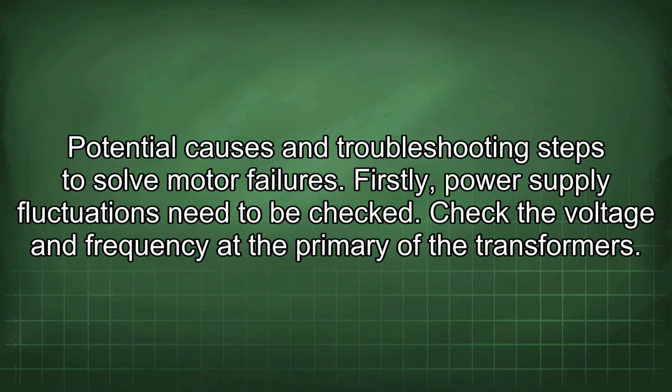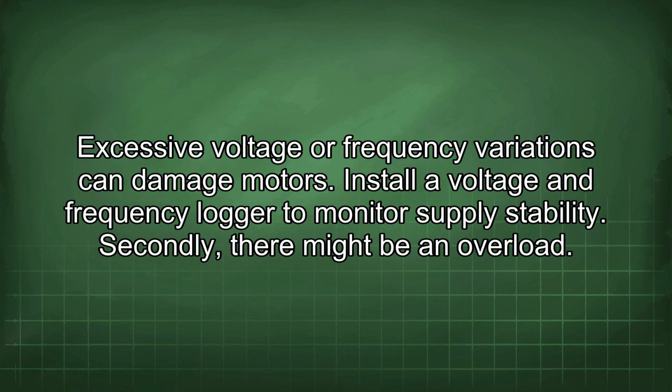Potential causes and troubleshooting steps to solve motor failures. Firstly, power supply fluctuations need to be checked. Check the voltage and frequency at the primary of the transformers. Excessive voltage or frequency variations can damage motors. Install a voltage and frequency logger to monitor supply stability.